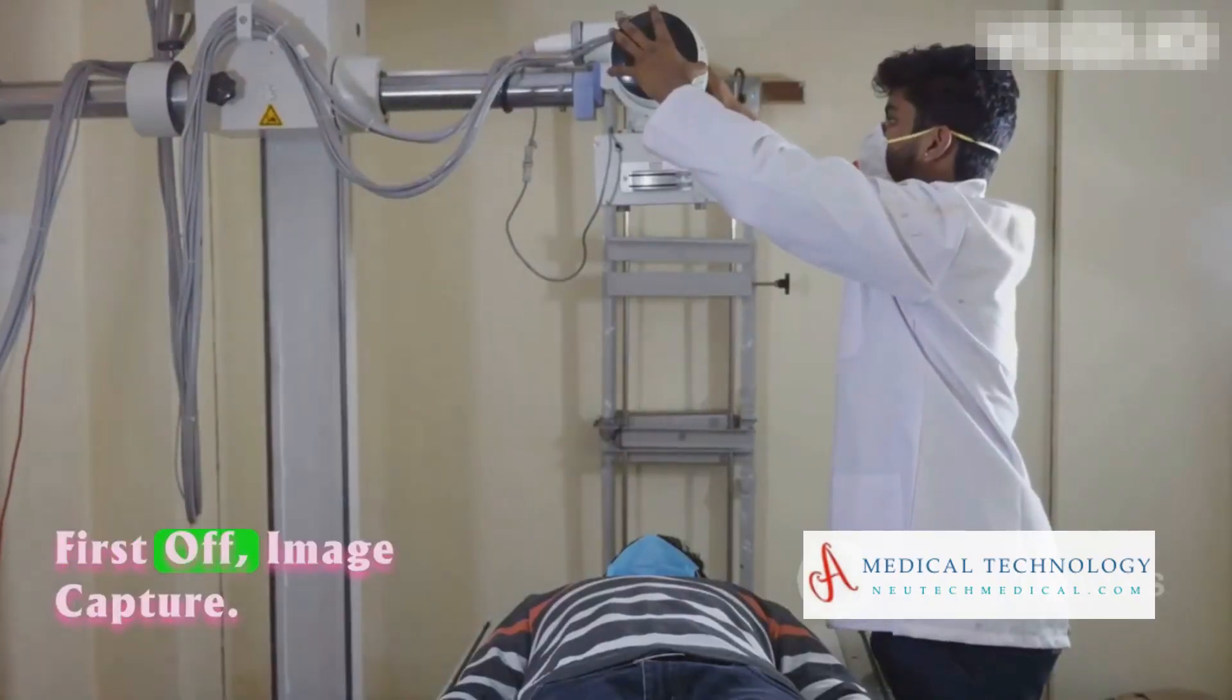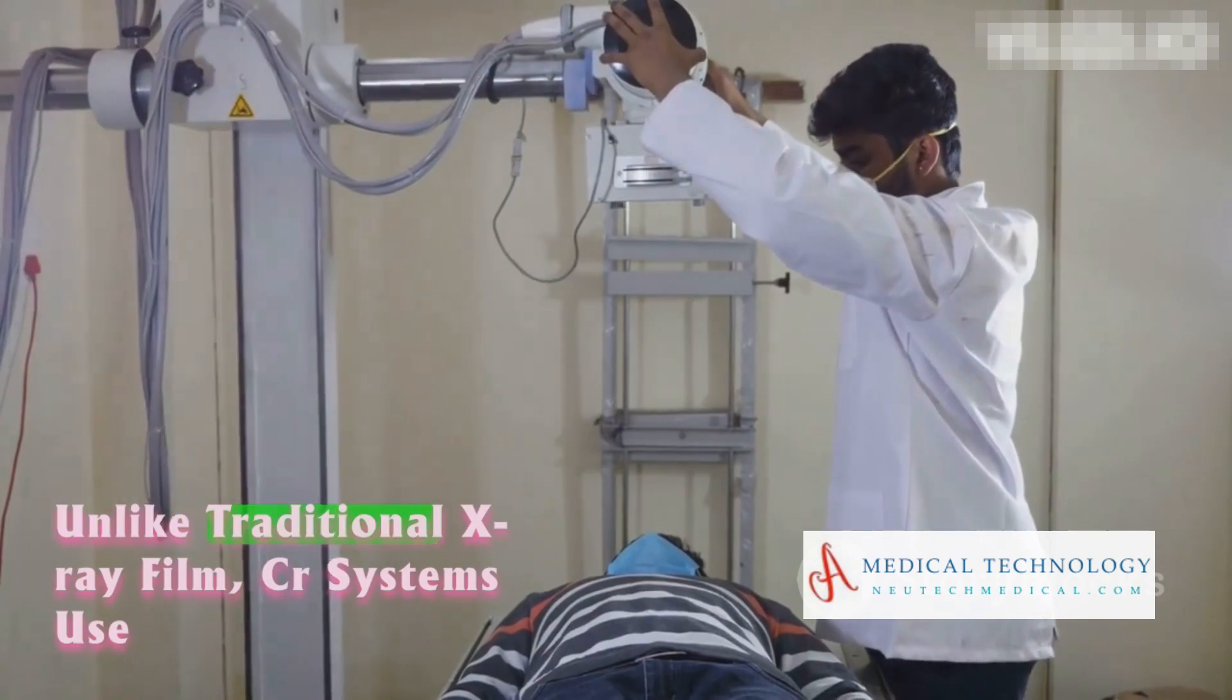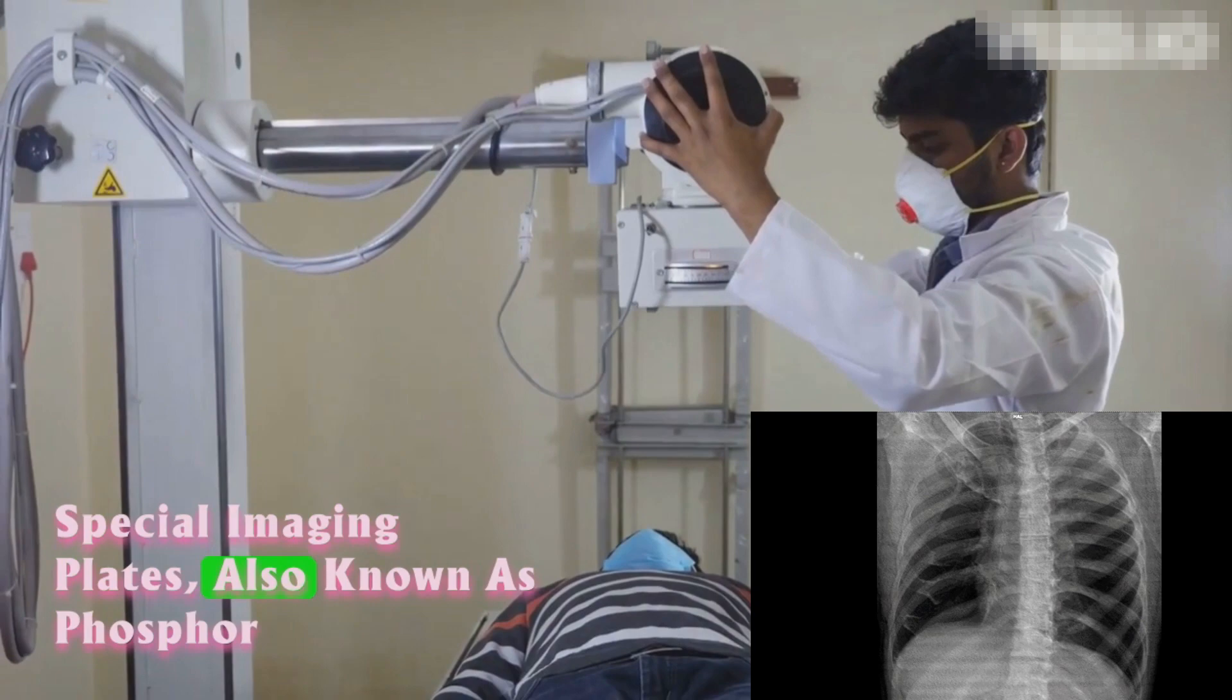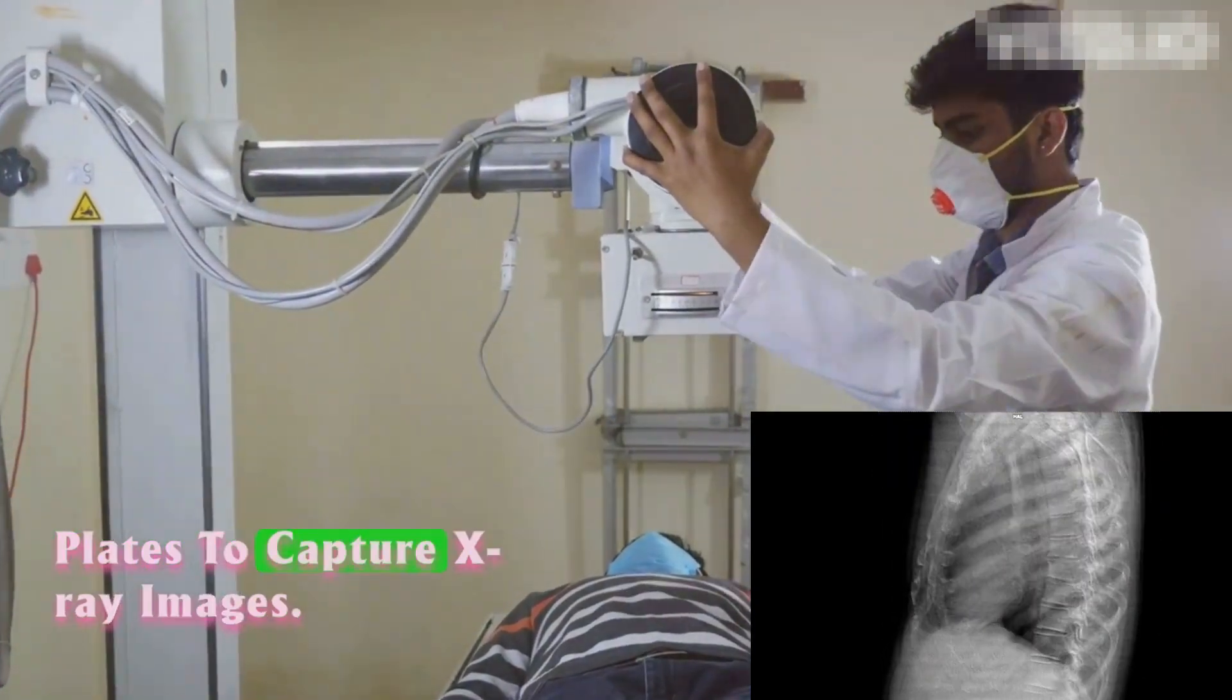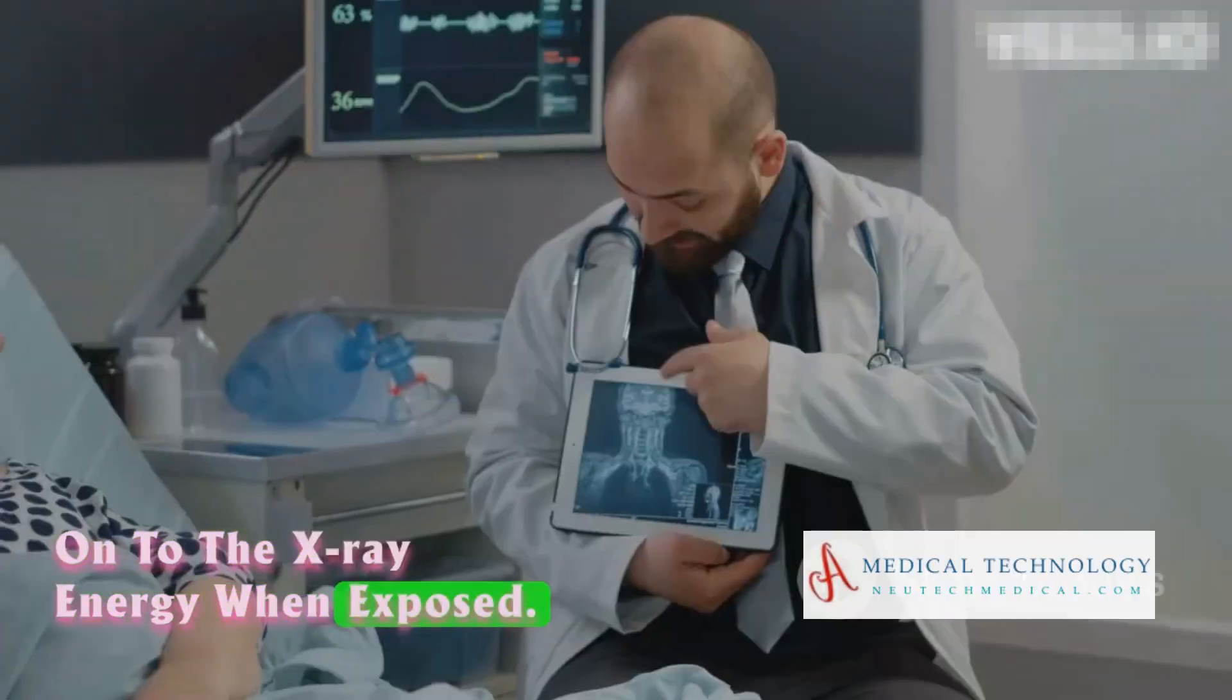First off, image capture. Unlike traditional X-ray film, CR systems use special imaging plates, also known as phosphor plates, to capture X-ray images. These plates have a phosphor layer that holds on to the X-ray energy when exposed.